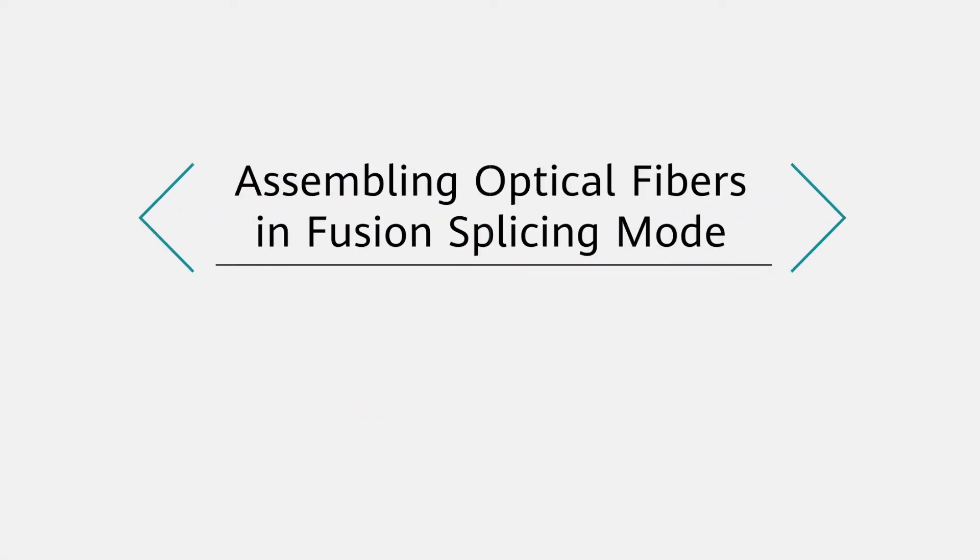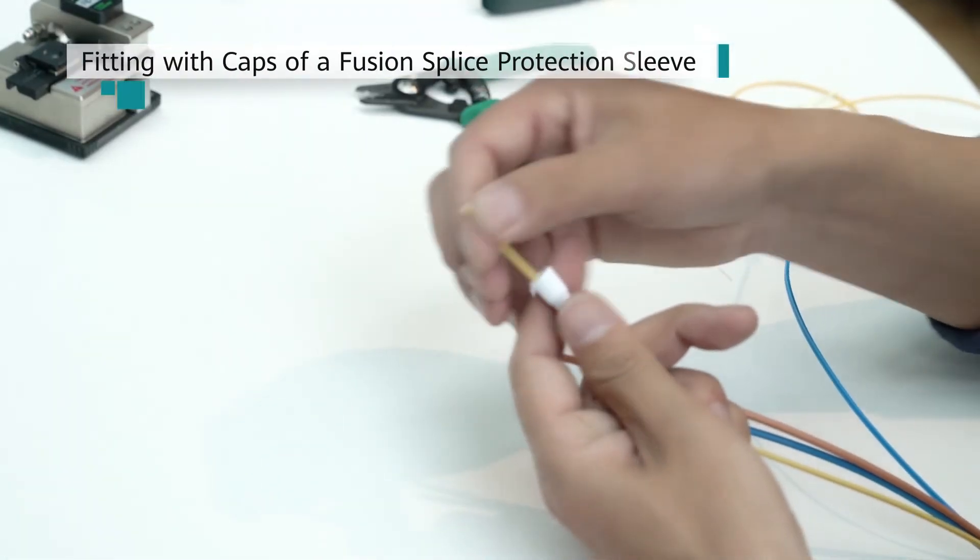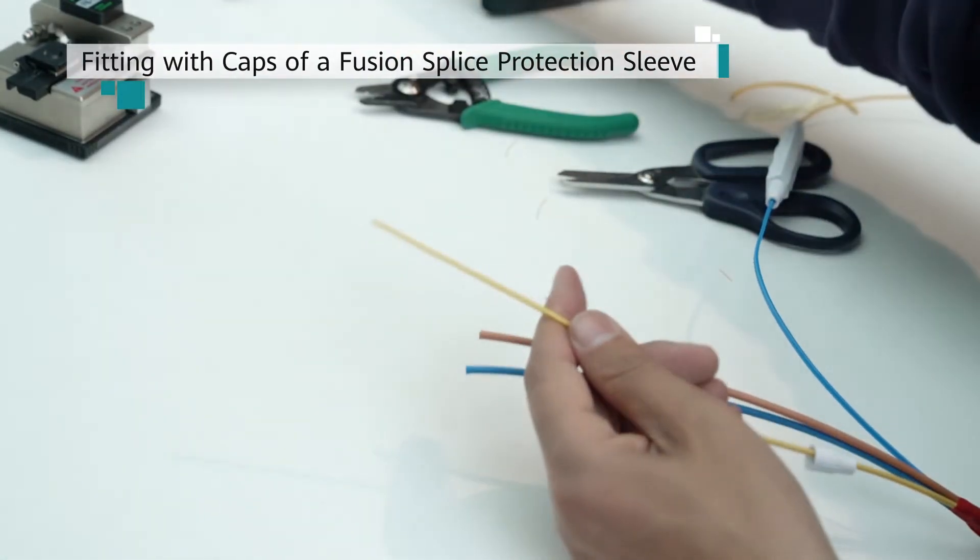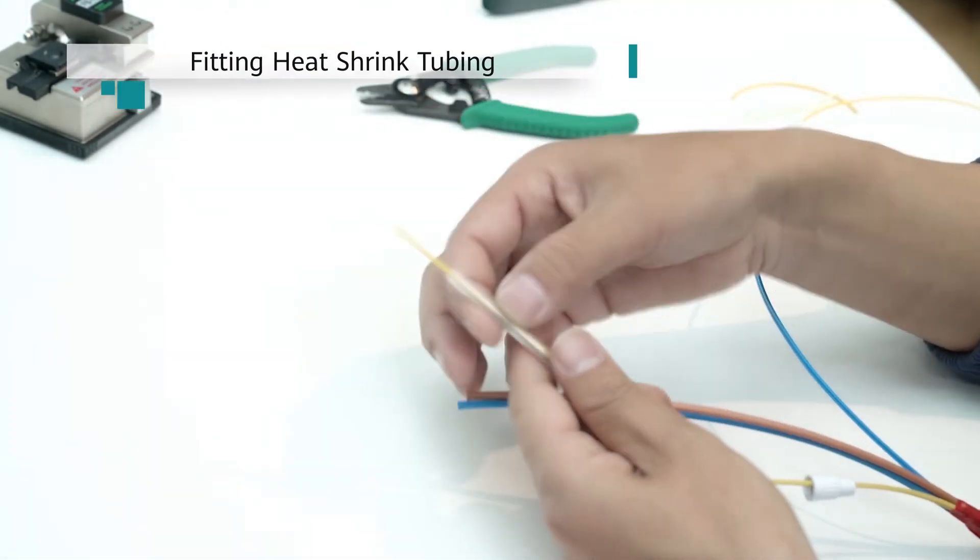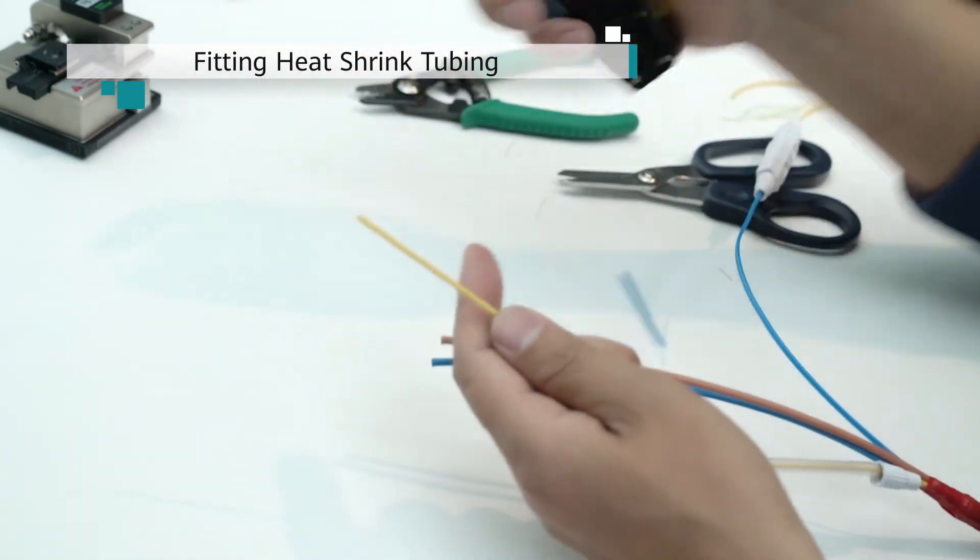Assembling optical fibers in fusion splicing mode. An optical fiber can also be assembled in fusion splicing mode. Feed one end of an optical fiber and one end of a pigtail through the caps of a fusion splice protection sleeve. Additionally, feed the optical fiber or pigtail through 60 mm of heat shrink tubing.